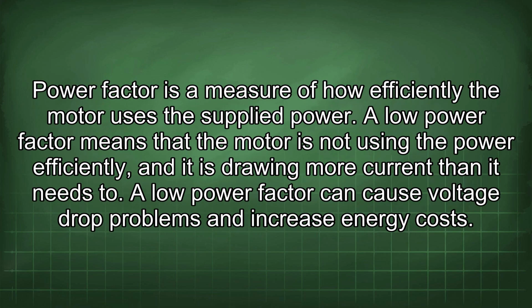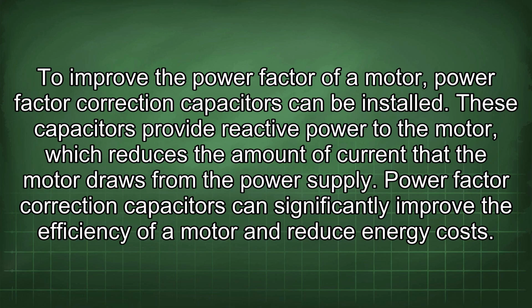Power factor is a measure of how efficiently the motor uses the supplied power. A low power factor means that the motor is not using the power efficiently and it is drawing more current than it needs to. A low power factor can cause voltage drop problems and increase energy costs. To improve the power factor of a motor, power factor correction capacitors can be installed. These capacitors provide reactive power to the motor, which reduces the amount of current that the motor draws from the power supply. Power factor correction capacitors can significantly improve the efficiency of a motor and reduce energy costs.